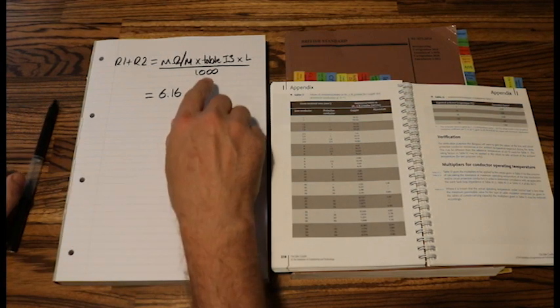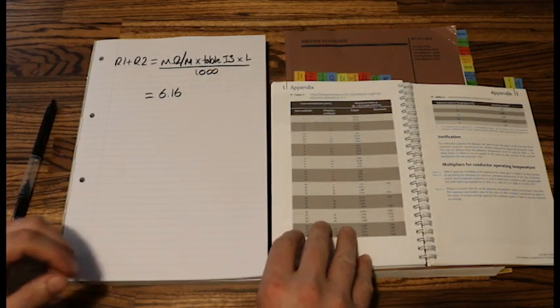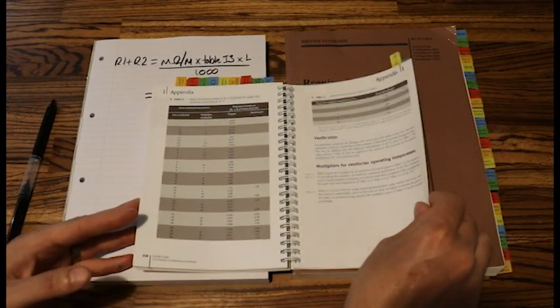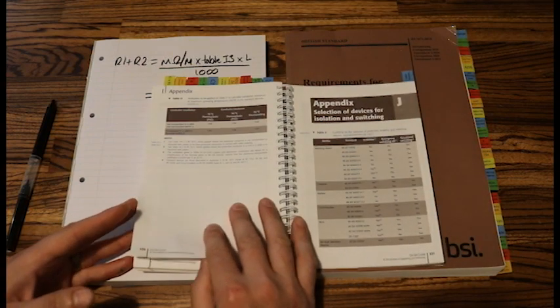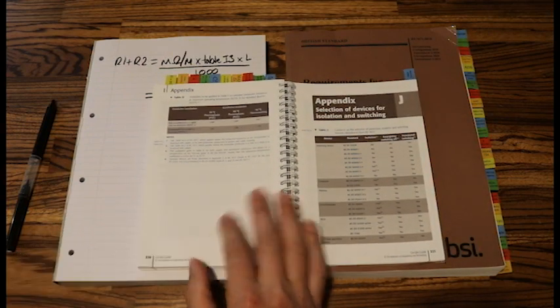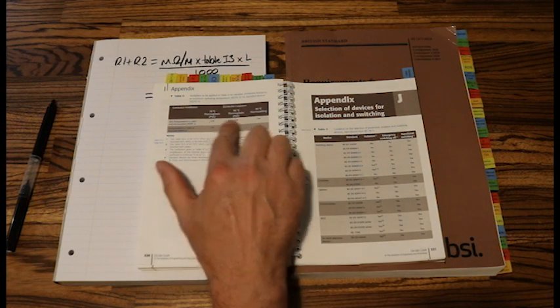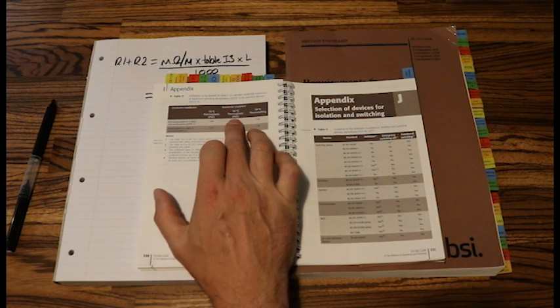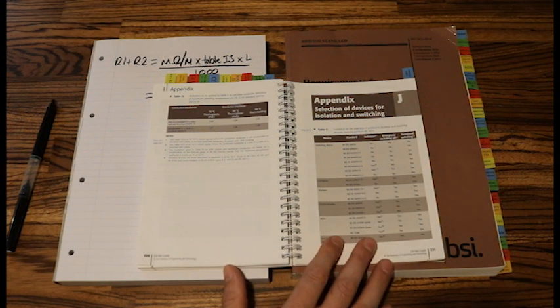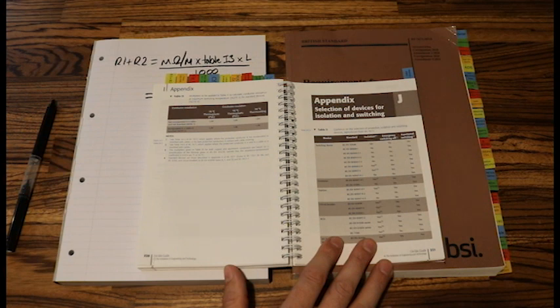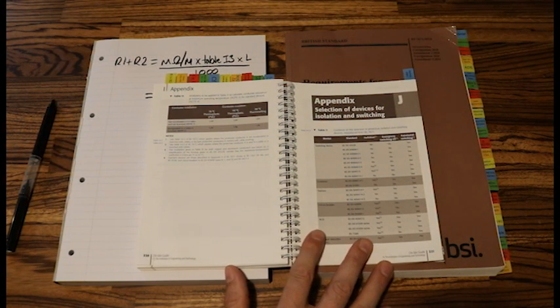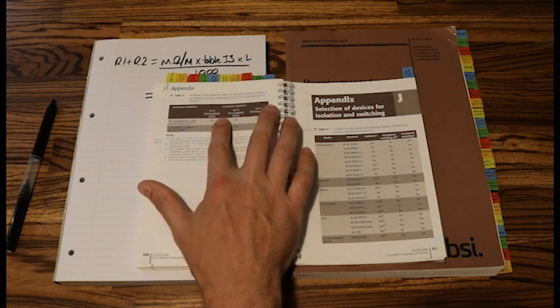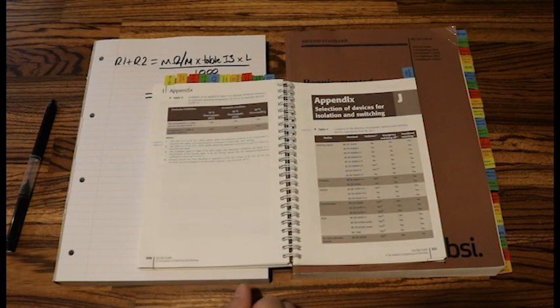And now I need to take the multiplier from table I3, which is just on the next page. Table I3, the multipliers. Now we've got a choice of cables. If we've got 70 degree thermoplastic or 90 degree thermoplastic. In your cable calculation question it will tell you what type of cable you're using. If the question doesn't tell you what type of cable you're using, always assume that we are using 70 degree thermoplastic. That is the standard type of cable we get.